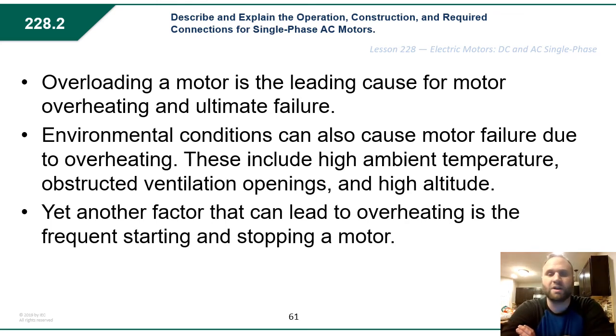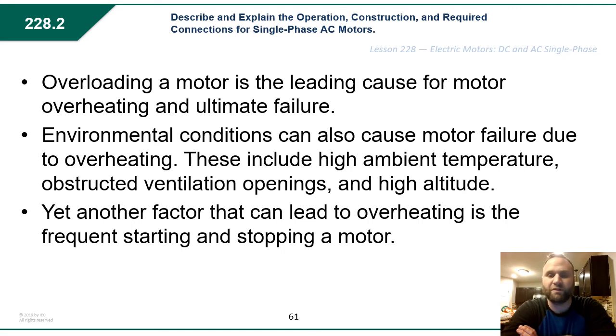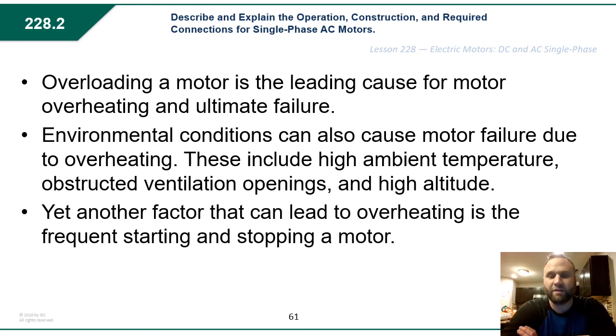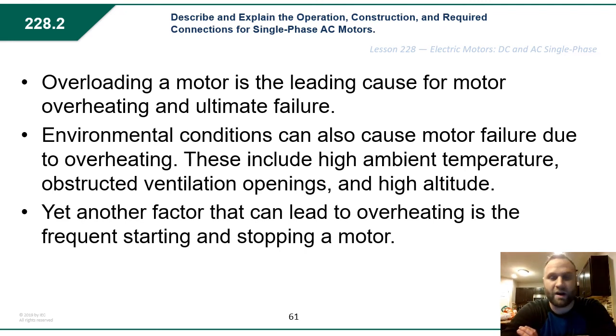Overloading a motor is the leading cause of motor overheating and failure. Environmental conditions can also cause motor failure due to overheating, including high temperatures or high altitudes where the motor may not be able to cool down adequately. Another factor that can lead to overheating is the frequent starting and stopping of a motor — the on and off again cycling is what breaks it down.